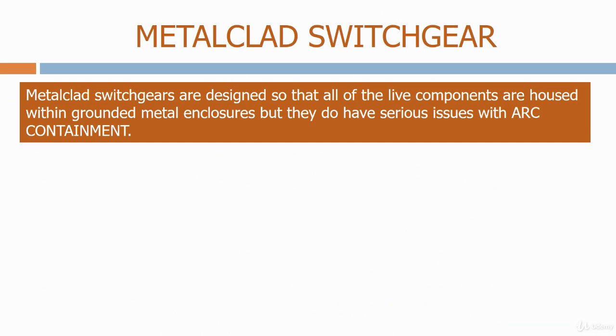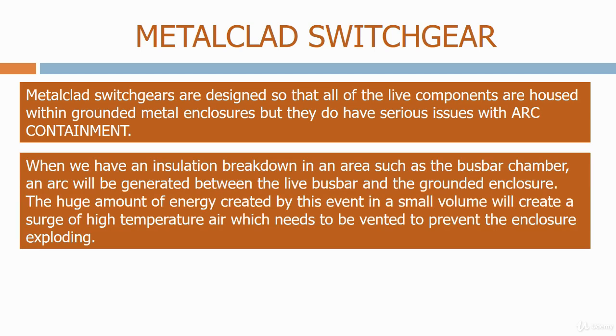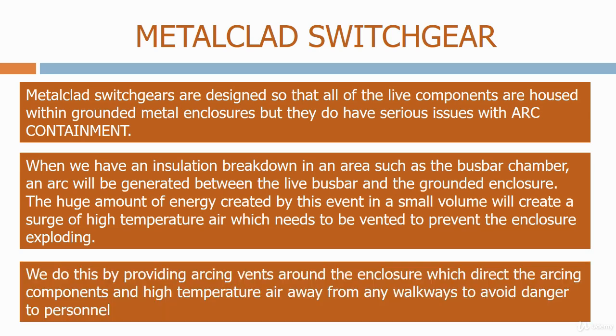Metalclad switchgears are designed so that all of the live components are housed within grounded metal enclosures, but they do have serious issues with arc containment. When we have an insulation breakdown in an area such as the bus bar chamber, an arc will be generated between the live bus bar and the grounded enclosure. The huge amount of energy created by this event in a small volume will create a surge of high temperature air, which needs to be vented to prevent the enclosure exploding. We do this by providing arcing vents around the enclosure, which direct the arcing components and high temperature air away from any walkways to avoid danger to personnel.